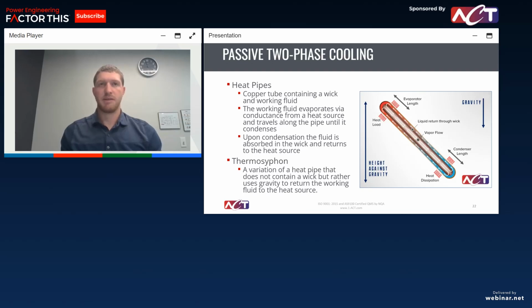So thermosyphon is basically a variation of a heat pipe. It does not contain that wick, but rather uses gravity to return that working fluid to the heat source. So a thermosyphon is dependent on the orientation of the system. It needs to have gravity to do its fluid movement, so your condenser will always have to be above your evaporator.